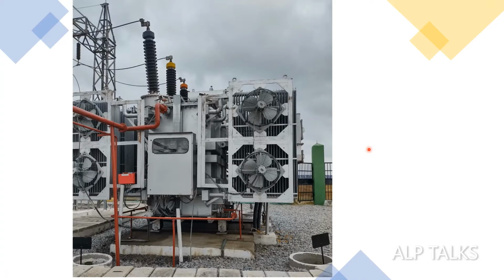This is a power transformer. This is a 25 megawatt plant. So in this plant, as of now, we have four inverter duty transformers and one power transformer. This power transformer capacity is 20 by 22 MVA. This is 33 by 110 kV, so these bushings are for 110 kV. We have fans set up for 22 MVA.